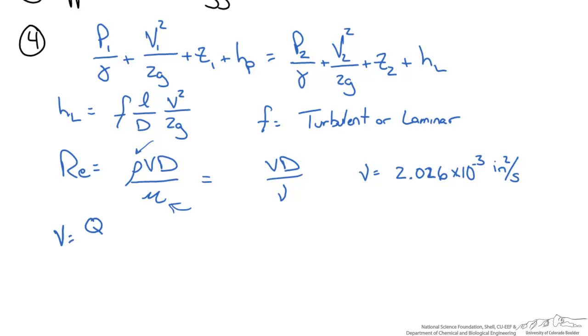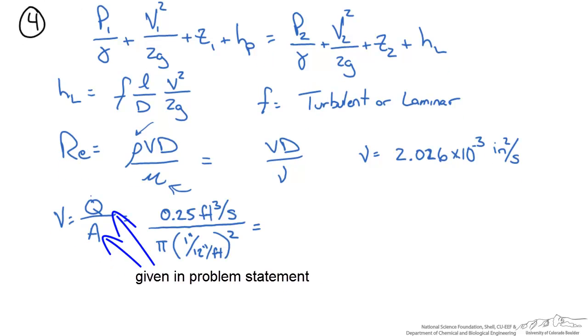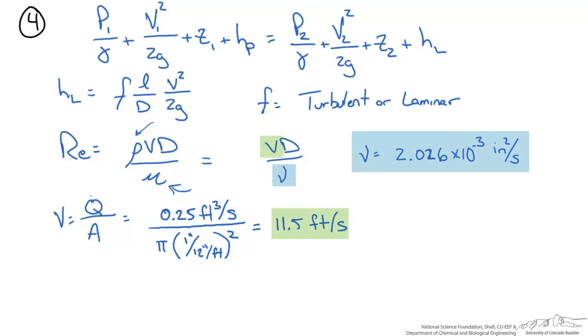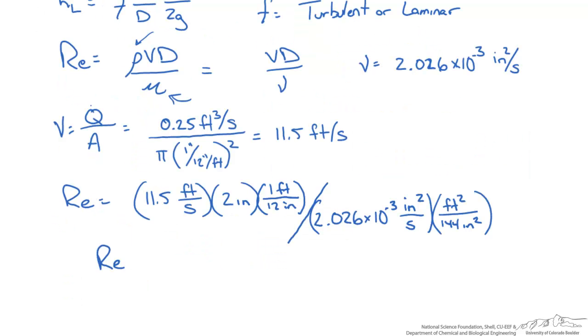The velocity of our fluid can be calculated as volumetric flow rate over cross-sectional area. When we do this calculation we get a velocity of 11.5 feet per second. Now we have velocity and kinematic viscosity. When I calculate the Reynolds number I get 1.4 × 10⁵, which is greater than 2,100 for the transition from laminar to turbulent flow. We can safely say this flow is turbulent.